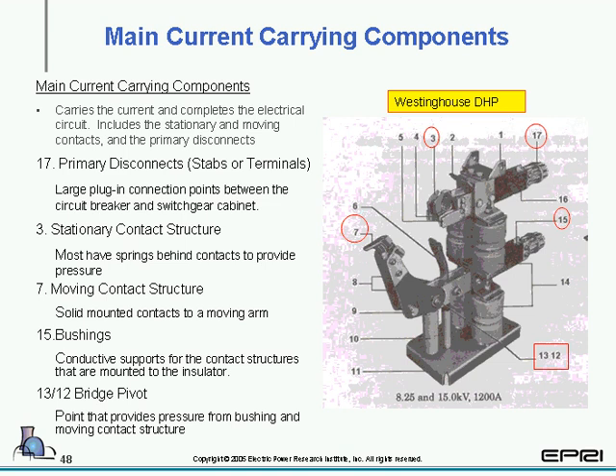Obviously, the main current carrying components carry the current from the line side to the load side of the breaker. And you'll see that on number 3, the stationary contact structure usually has springs mounted behind it for pressure when the number 7 moving contact comes up and strikes it. And that's what maintains the pressure between the moving and the stationary contacts. Also, we have 15, which is the bushings. The bushings provide insulation between the current-carrying parts and normally the frame of the breaker itself. And one of the other notes is the bridge pivot. This is a point that provides pressure from the bushings and the moving contact structures. The bridge pivot allows the moving contact structure to strike the stationary contact structure while allowing current to flow.